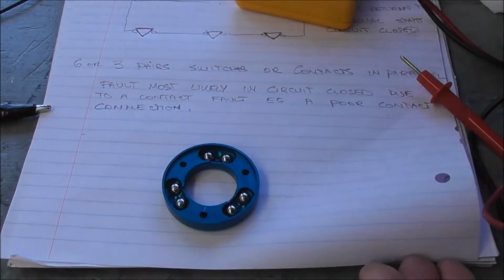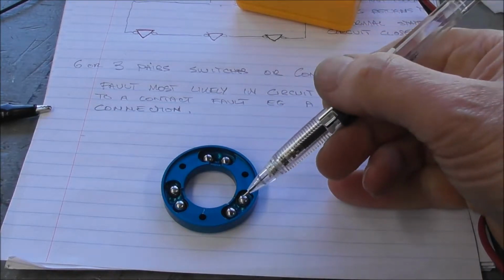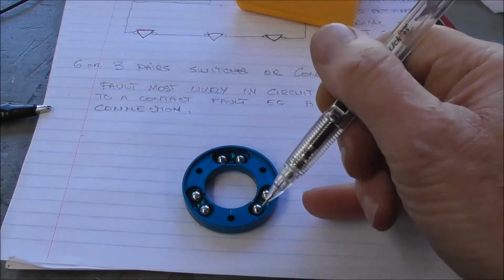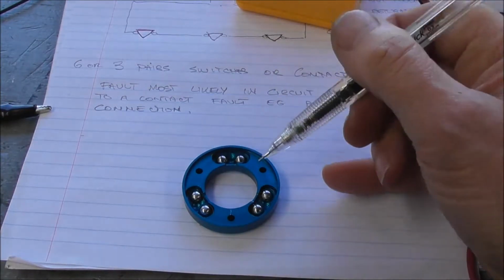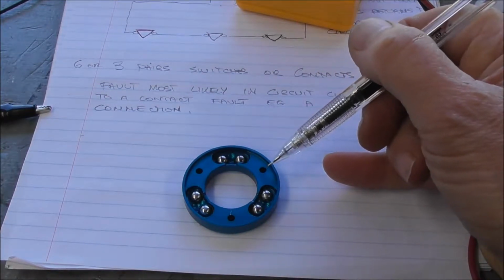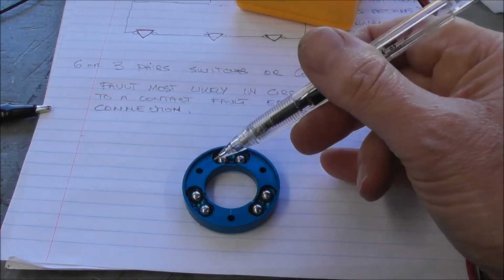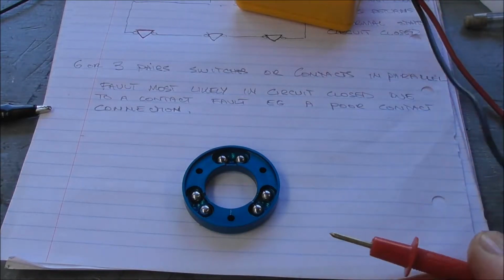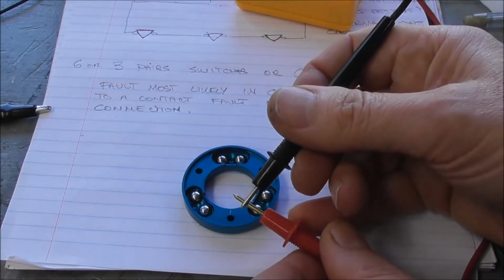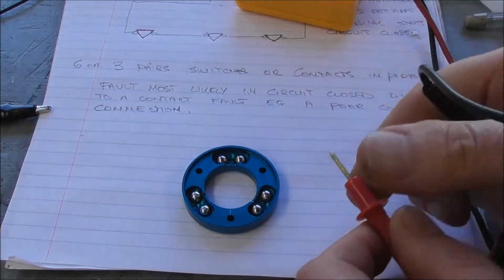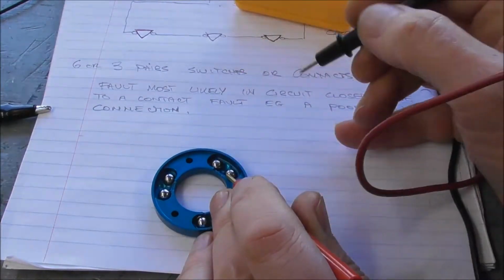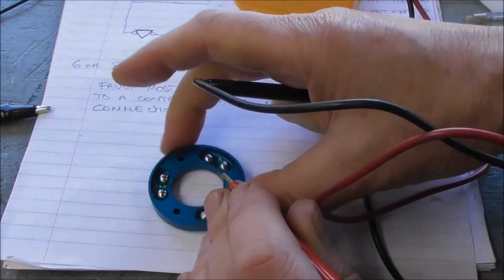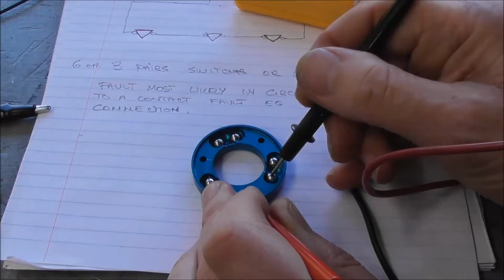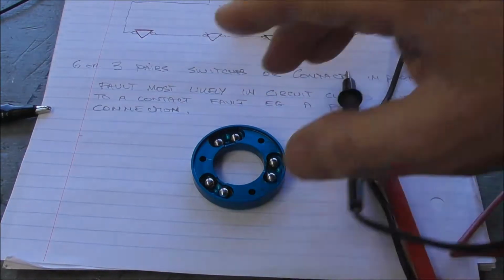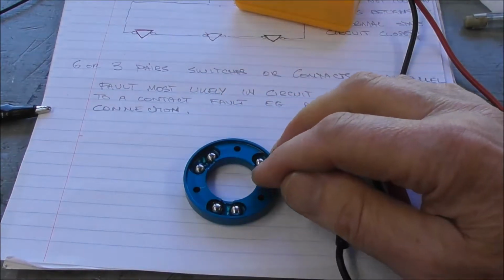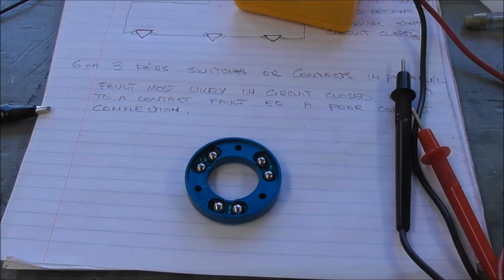So in the area of a short or an incorrect connection within the probe, we're just looking inside the end cap now. The 6 ball contacts should not be electrically connected to each other. So the end cap is anodized, and that's an insulated surface, and the balls should not be in contact with each other. And you could check that if you ever have a short problem. Again, you've got your circuit tester here, and you'd contact one ball and check the other balls. Contact the next ball and check the other balls. Just to check that it's never happened, but again, one day it might happen. There could be a connectivity between one ball and another, and again, that would mess up with the function of the probe.